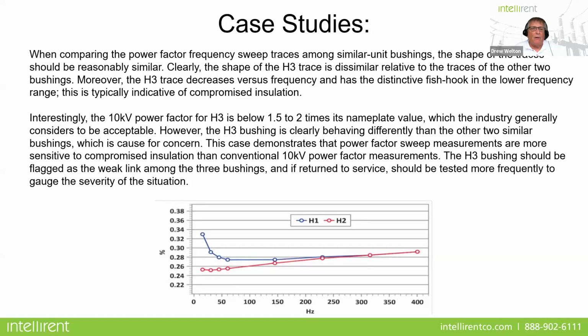So when comparing the power factor in these traces, interestingly, at 10 kV, the power factor of H3 is below 1.5 to 2 times its nameplate value, which, if you look at the industry standards, is considered acceptable. But when you see this fishhook approach, that would tell me that it should be flagged as a weak link among the three bushings.